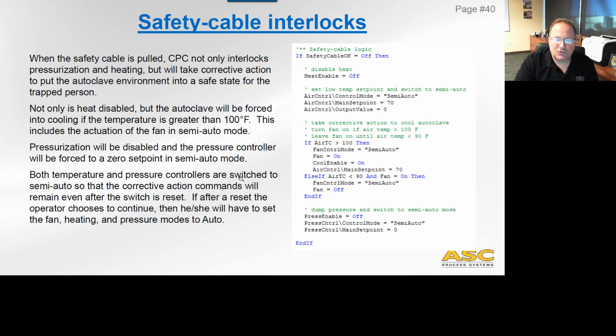And both temperature and pressure controllers are switched to semi-auto so that corrective action commands will remain even after the switch is reset. So even if they pull the safety cable and reset it, everything's still going to be going down to ambient conditions. They will have to actually go in and change control modes in the manual screen to get that to stop. So here's the code. If safety cable is not okay, is off, disable heating, change the air controller to semi-auto, put a 70 degree set point, output of zero.